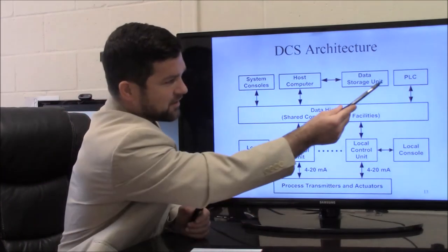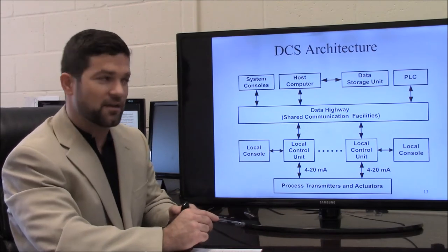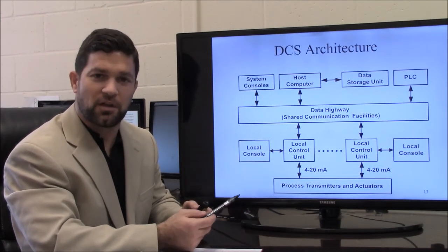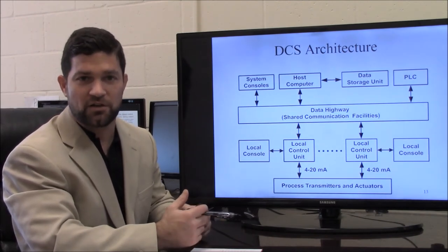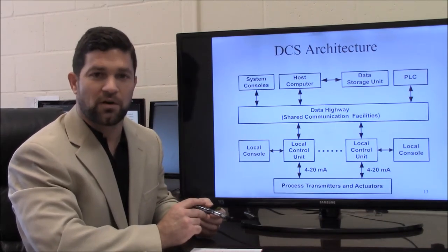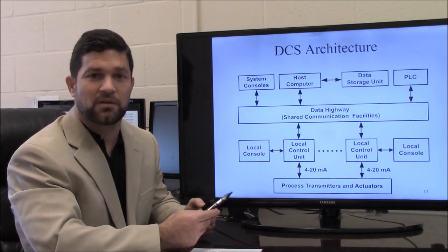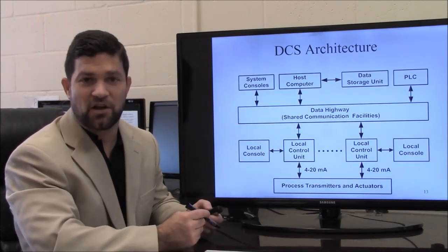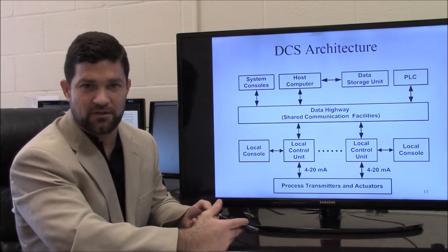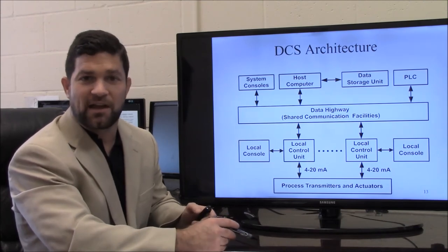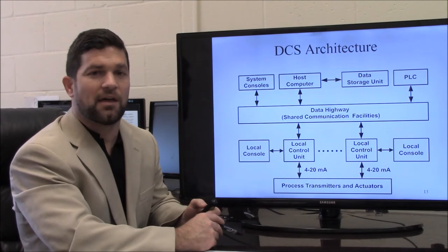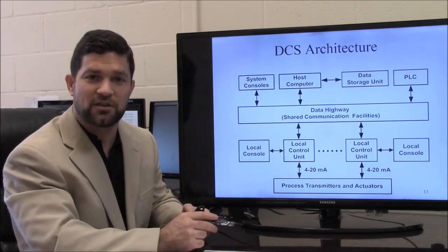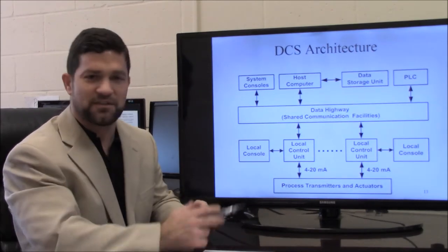One important thing to note on this slide is in the upper right-hand corner there's what's called a PLC — a programmable logic controller. These are controllers that use ladder logic, which is useful for things such as reactor startup, reactor shutdown, batch operation, and any sort of startup sequence. Ladder logic systems go through a series of logic commands, such as: fill the reactor until it reaches a target level, add steam until it reaches a target temperature, add reactant component one until a certain outcome is achieved. These programmable logic controllers can be integrated with DCS systems fairly seamlessly.